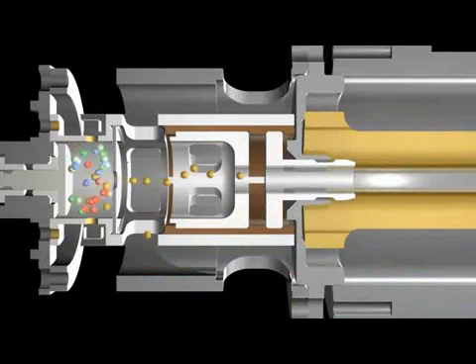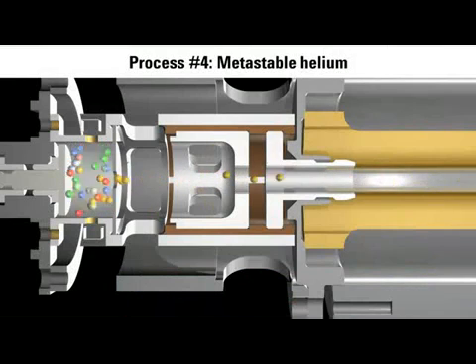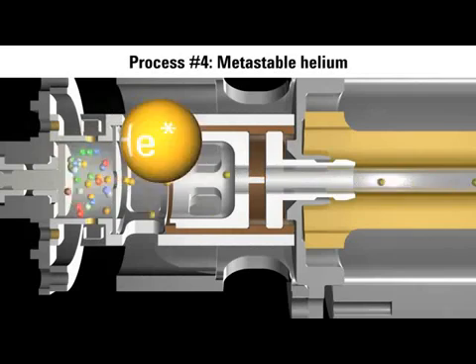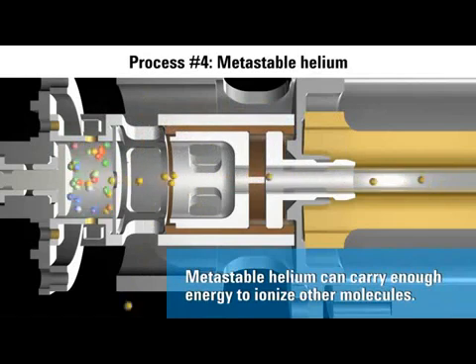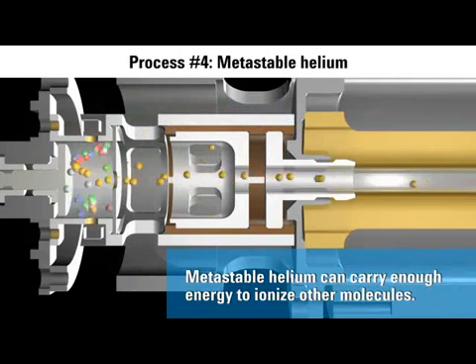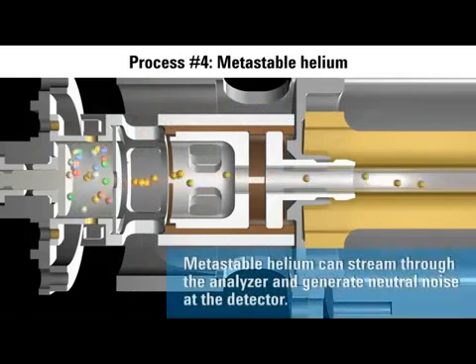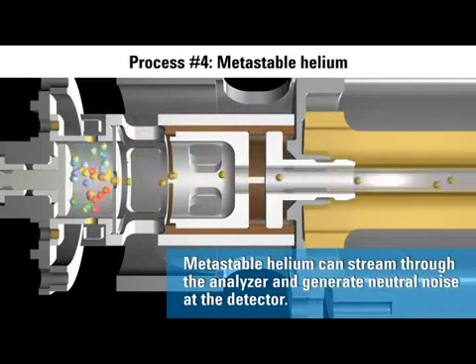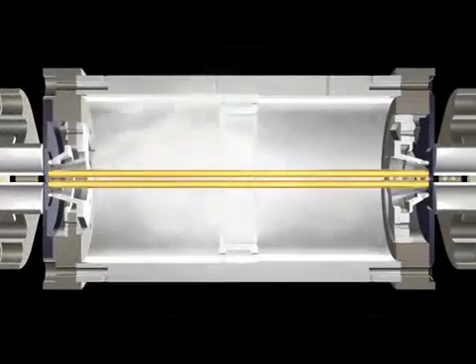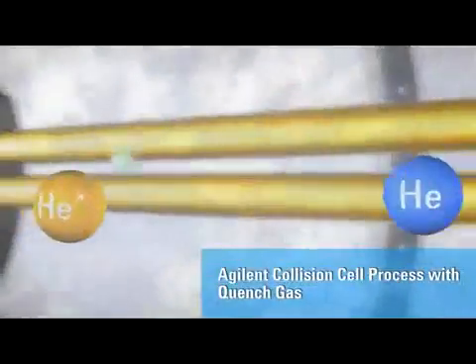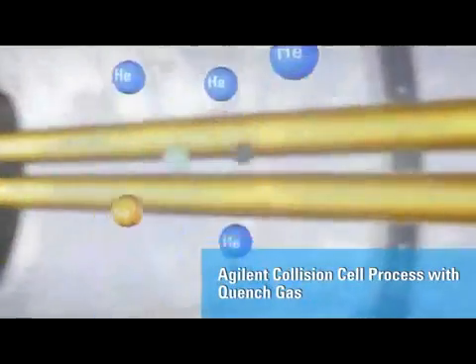Before continuing to the collision cell, one more process must be mentioned. An EI source produces a large number of highly energetic metastable helium atoms. These highly energetic atoms follow a random path like any other neutral until removed by the pump. Some will follow a path parallel to the analyzer and have a high probability of traversing the entire analyzer assembly to the HED-EM detector. During the development of the 7000, Agilent engineers realized a small flow of helium added to the nitrogen collision gas was a very effective way to reduce the transmission of metastable helium through the collision cell. We call this patent-pending solution helium quenching.